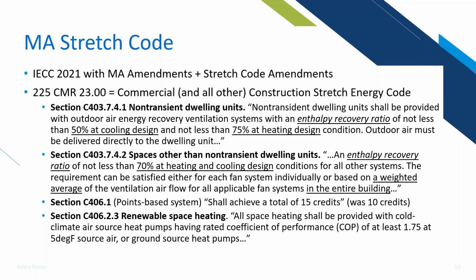And one of the really big differences here is the next section, which is spaces other than non-transient dwelling units. An enthalpy recovery ratio of 70% in heating and cooling must be required for the entire building, basically. Now, that's different than it used to be. This is a big change because it used to be that you could get away with a lesser cooling ERR than the heating, and now you need 70% ERR in both heating and cooling at the design conditions.